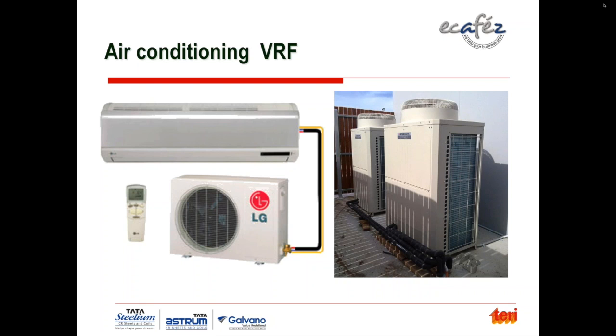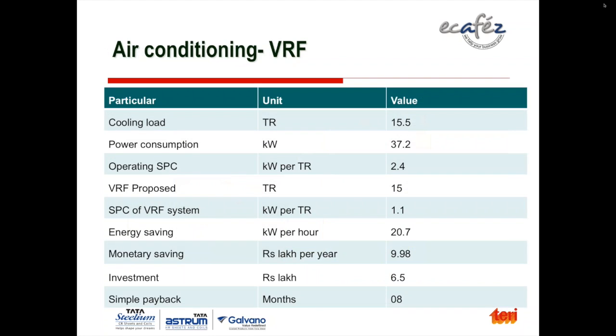Essentially, the cooling load is dictated by the amount of refrigerant flow in the system. This is about a 15 TR air conditioning system. Power consumption was, as you can see, 37 kilowatts. So it was 2.4 units per TR. That was the consumption. The proposed capacity was again the same 15 TR, but the specific energy consumption in the VRV system was 1.1.